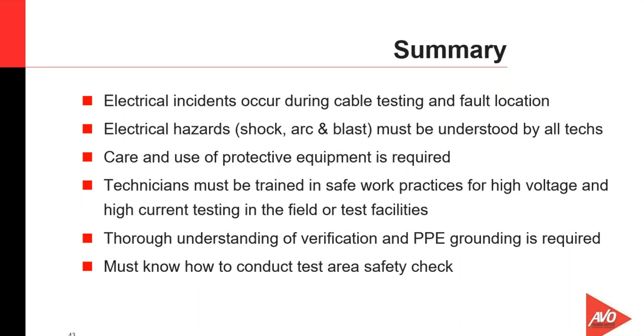Technicians need to be trained in all the safe work practices for high voltage, high current testing in the field and test facilities. We have numerous places to go look to get that information. The IEEE Yellow Book, which was later converted to an IEEE standard, has 3007.1, point 2, and point 3. Point 3 is the Electrical Safe Work Program. The Electrical Safe Work Program is mandated. It has to be written. High current and high voltage testing would definitely be a part of the Electrical Safe Work Program.